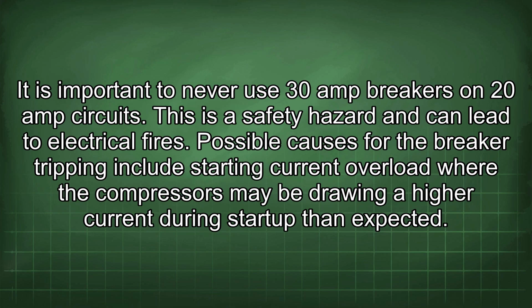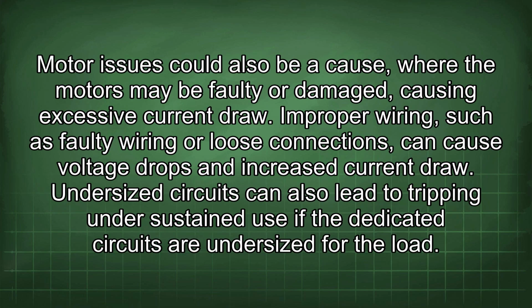It is important to never use 30 amp breakers on 20 amp circuits. This is a safety hazard and can lead to electrical fires. Possible causes for the breaker tripping include starting current overload, where the compressors may be drawing a higher current during startup than expected. Motor issues could also be a cause, where the motors may be faulty or damaged, causing excessive current draw. Improper wiring, such as faulty wiring or loose connections, can cause voltage drops and increase current draw. Undersized circuits can also lead to tripping under sustained use if the dedicated circuits are undersized for the load.